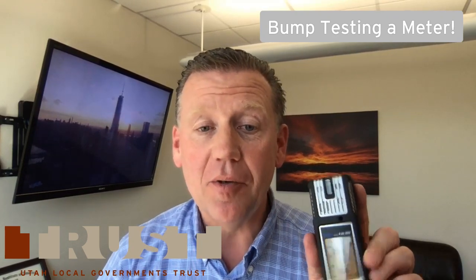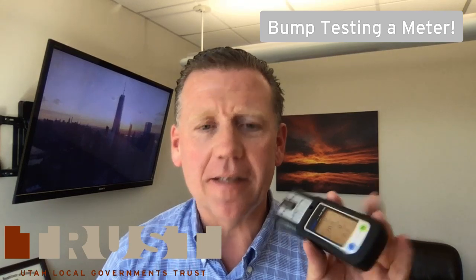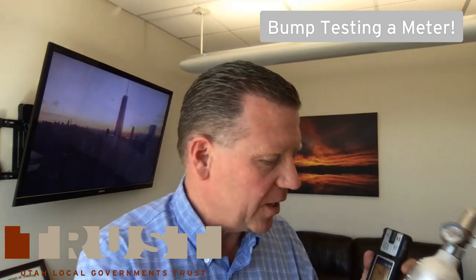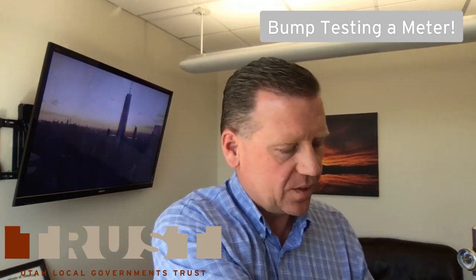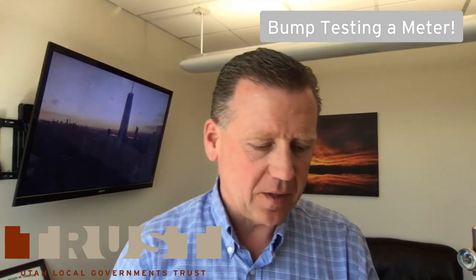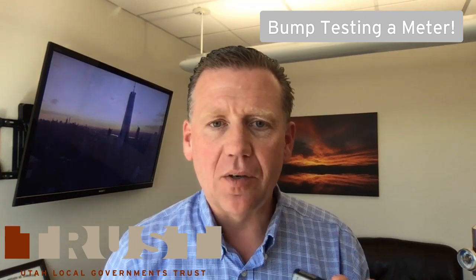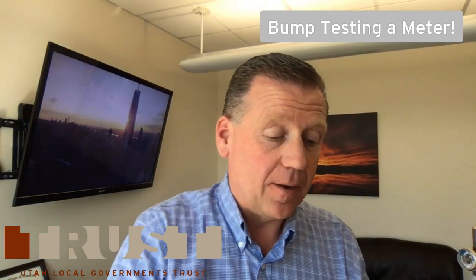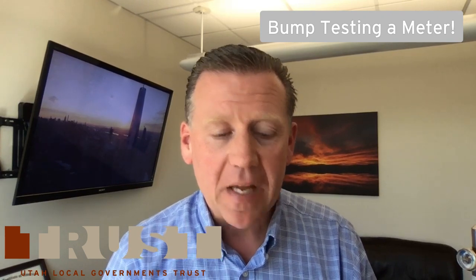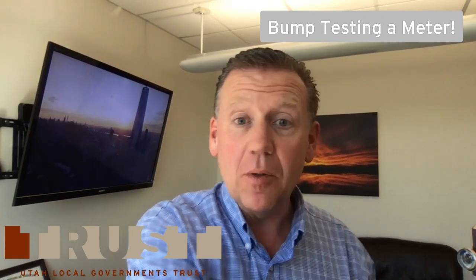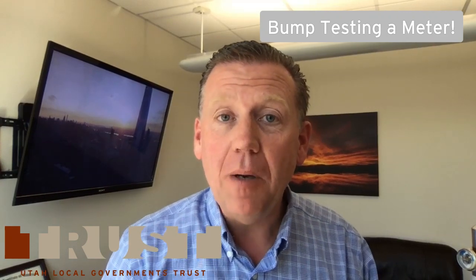Some of you will have a bump test unit that you can just plug this in. Those are really handy. But we can do this really simply by using our bottle of calibration gas and our calibration unit, whether it's a pump or a specific calibration unit. This one's pretty close, and so I will just run it through a calibration cycle. Within your organization, you should have somebody that is trained to do a calibration, and that's as simple as it is to do a bump test.